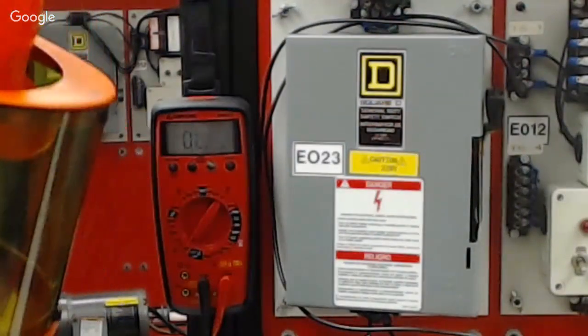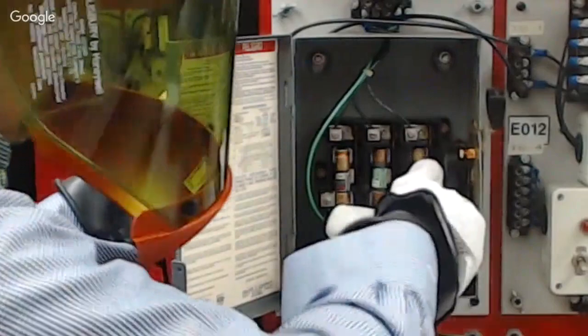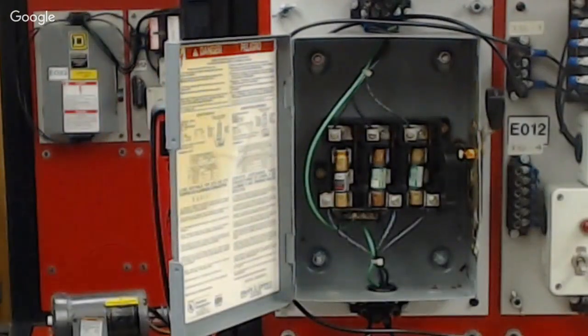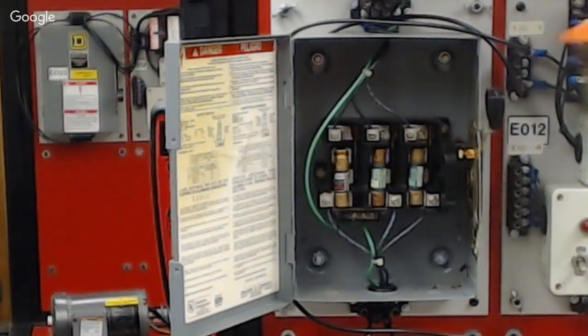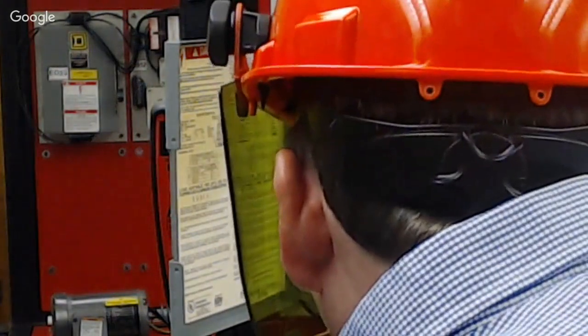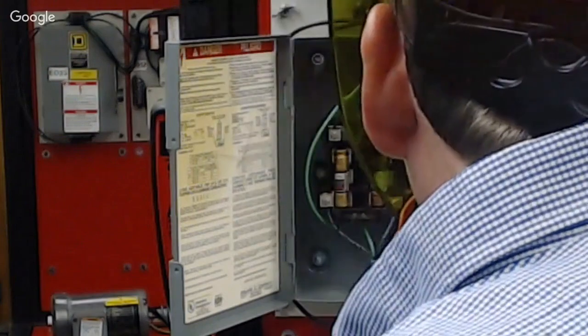Now, sometimes you can get tricked because if you have a control transformer hooked up to this, by the way, if I was checking this on a standard industrial system of 480, I'd be reading 480 across the different fuses, but to ground, or across a fuse, I'd be reading 277 on one phase. I have a 220 volt three-phase system here, so we're not reading that, or 208 volt. So let's see if we can actually check this to ground.